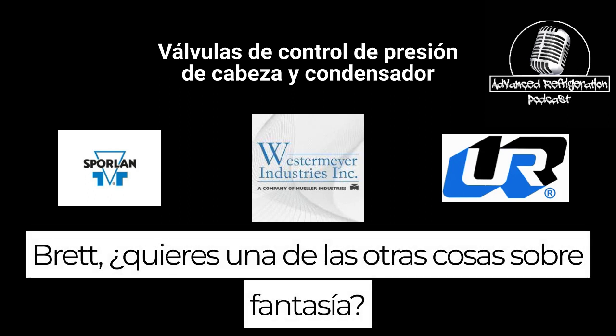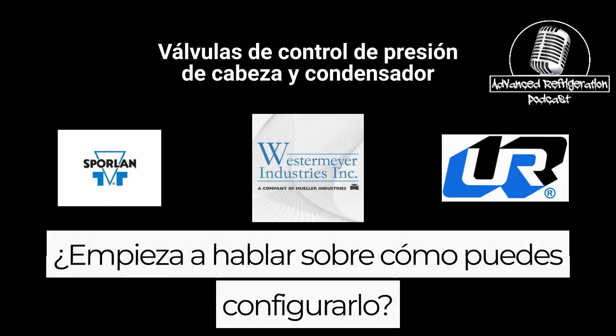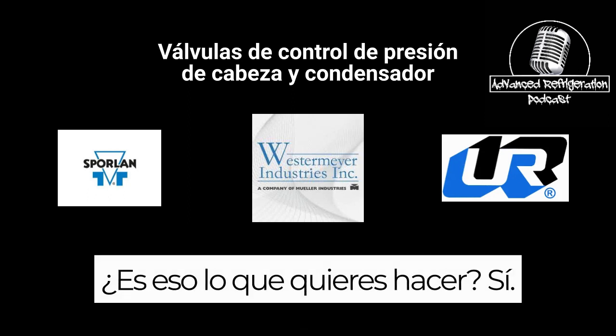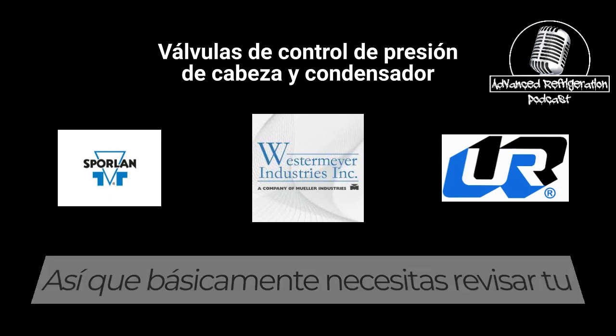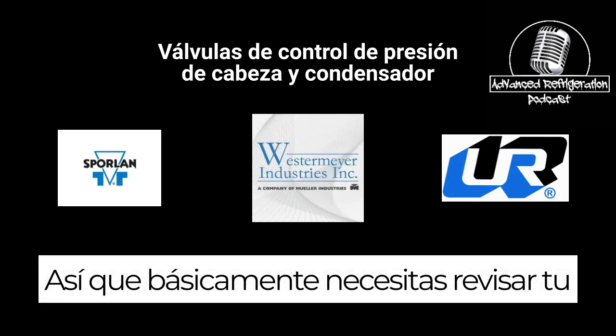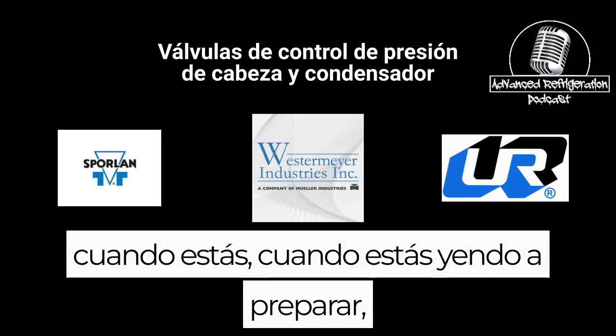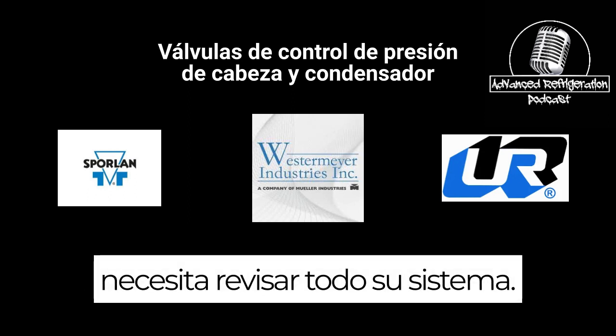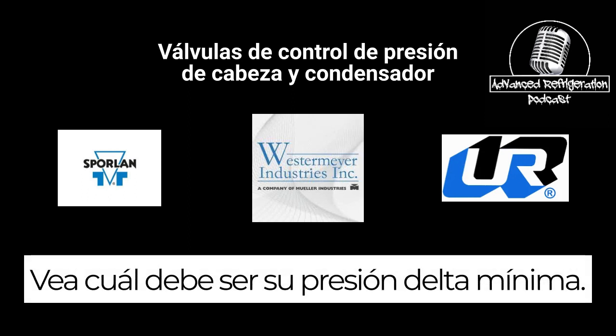Brett, one of the other things about fan cycling, should I start talking about how you can set it? Is that what you want to do? Yeah. So basically, when you're going over setting up fan cycling, you need to look over your entire system and see what your minimum delta pressure needs to be.